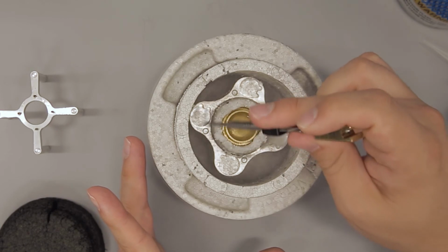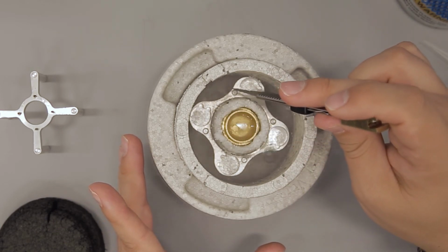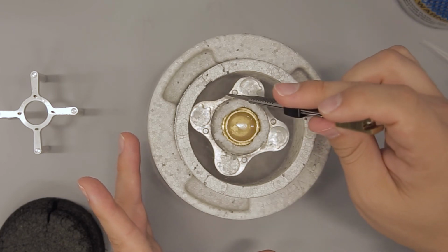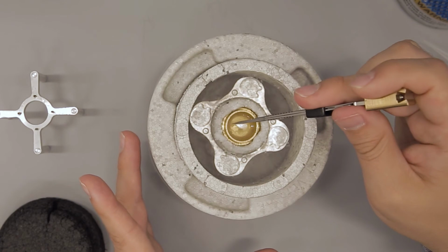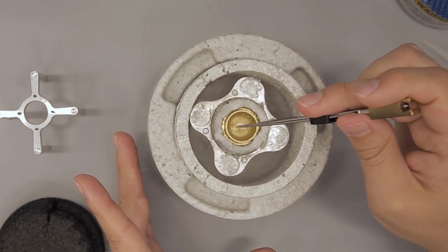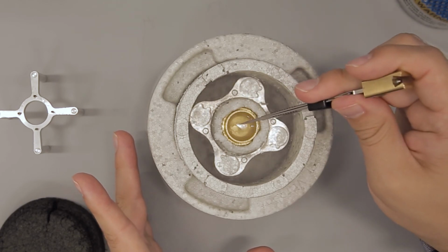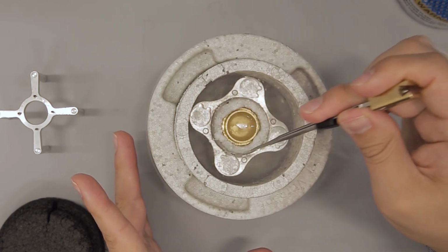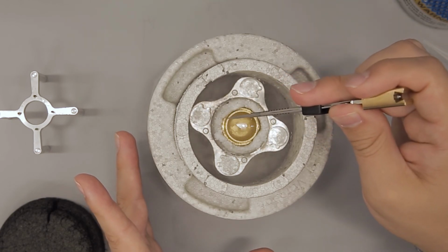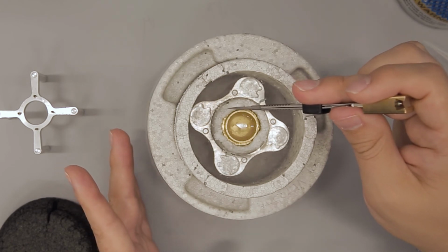So to sum up, the source of contamination coming from the vitrification process can be large ice crystals that come from dirty nitrogen that are floating around, and they can be visible by eye, and then they're very, very large. Or they can be smaller, the ones that you don't see but are also present there. You can have finer ice crystals. Normally they're round, they're not faceted in the microscope, and those come actually from the vapor. So the longer you keep the grid here in the vapor, the more chances you will have that you will pick up that. So that's a fine contamination of small particles, normally round, grouped together.